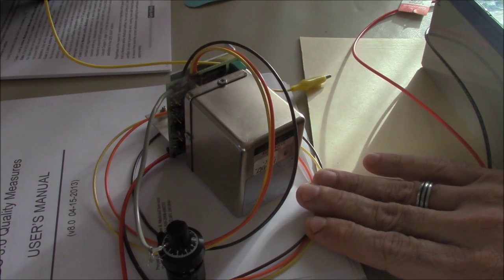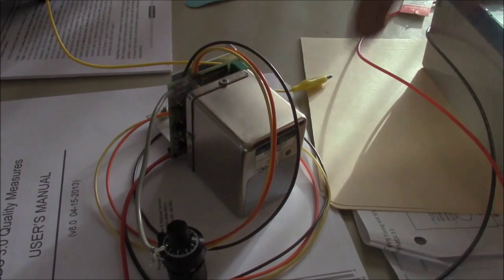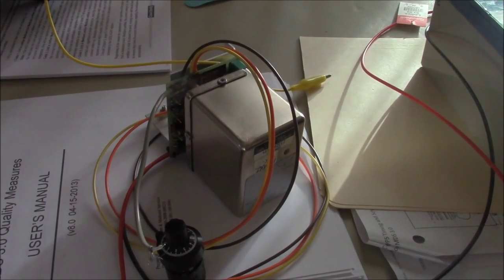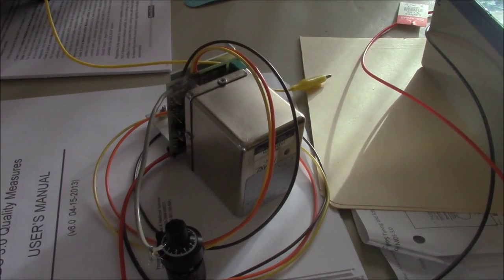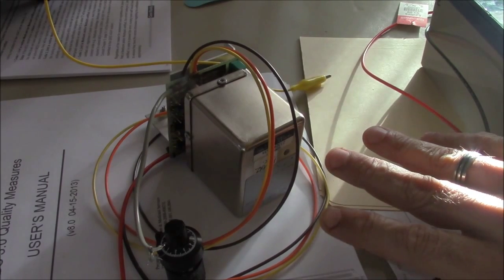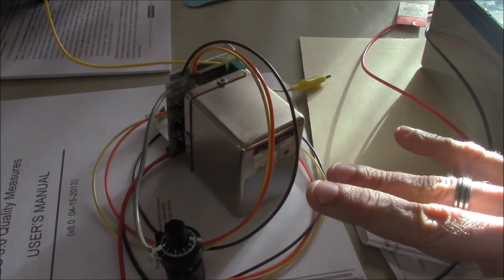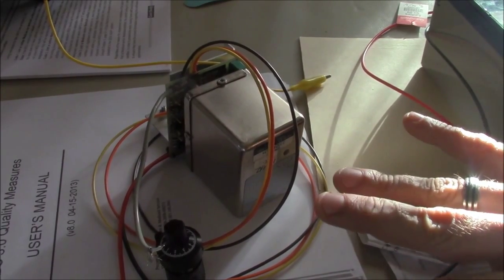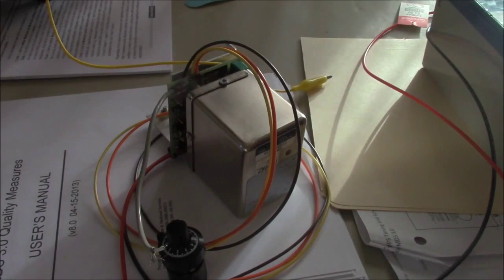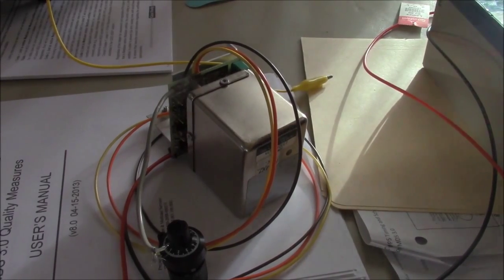In the instructions - you can find the instructions online for these easy enough, it's just a PDF, and if I think about it I'll put it down below in the description field - they tell you not to put it in any place where the ambient air temperature would change, or basically in a nutshell, keep it away from breezes or fans or anything like that. This is a perfect example of a bad location out here in the open, but we're just playing around.